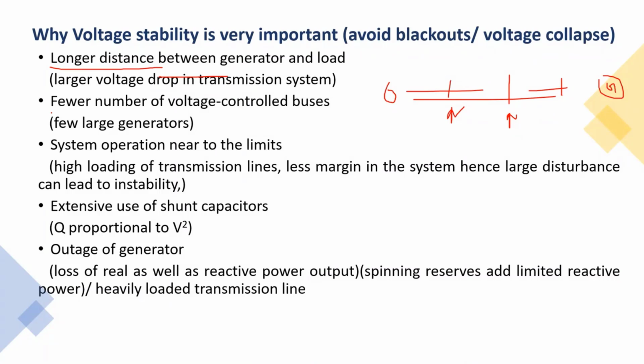And we have a lower number of voltage control points, right? Voltage can be controlled either at the generator or at any kind of FACTS devices like STATCOM or SVC, or a synchronous condenser. There you can control the voltage through dynamic active and reactive power control. For controlling the voltages, you need very dynamic reactive power control. For that, if you have a generator or FACTS devices, you can do it. Otherwise, it will vary depending upon the power flow happening in the system, or how much active and reactive power compensation has been provided, or switched on or switched off at that particular node. So it will keep on varying, except at the generator and FACTS device substations. Otherwise, there is nowhere you are able to control it.